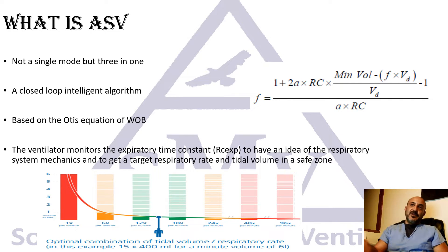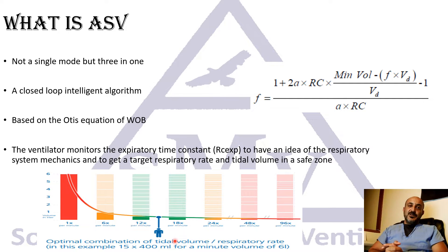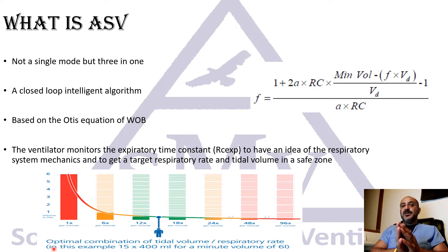The mode is based on the famous Dr. Otis equation of work of breathing from the 1950s — a complex mathematical equation that essentially asks: how do we achieve the least work of breathing? We either go with a high tidal volume and low respiratory rate, or a low tidal volume with a higher respiratory rate. The ventilator continuously monitors the expiratory time constant, which reflects resistance and compliance, giving a snapshot of respiratory mechanics. Based on this, the ventilator targets a safe tidal volume and respiratory rate to minimize work of breathing.